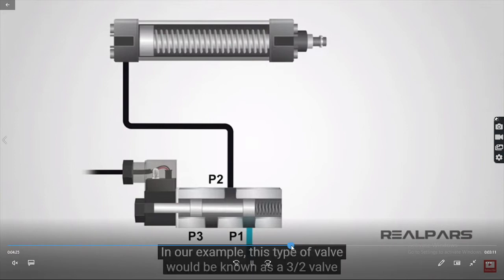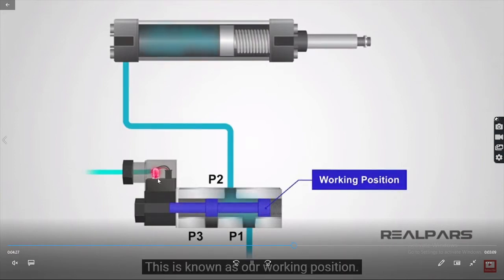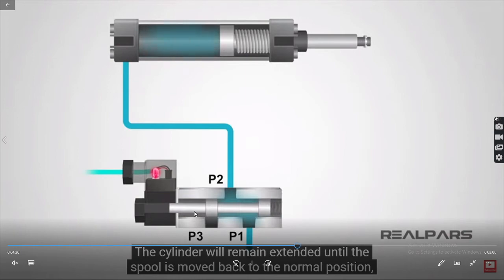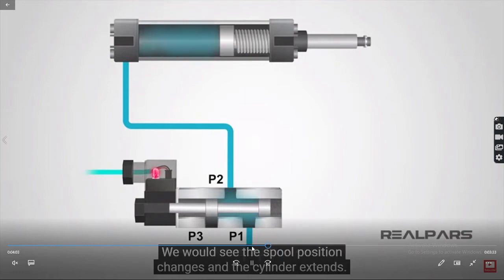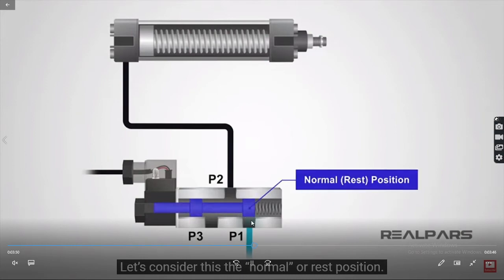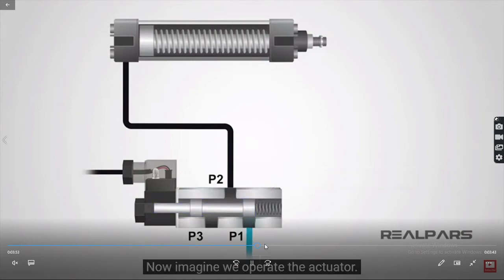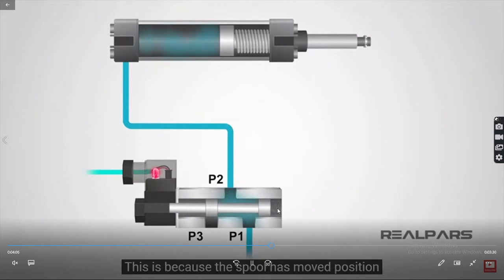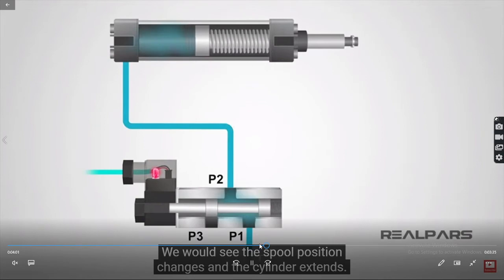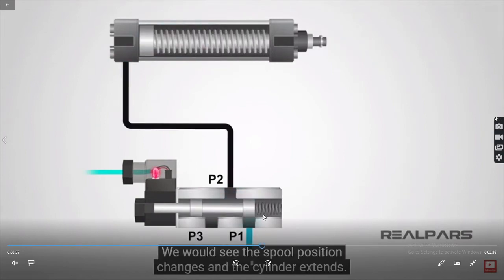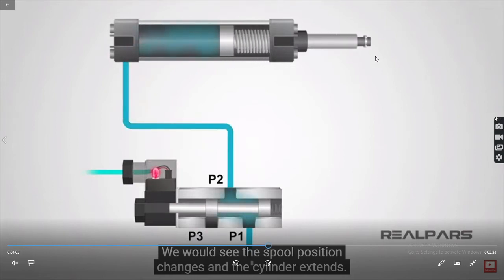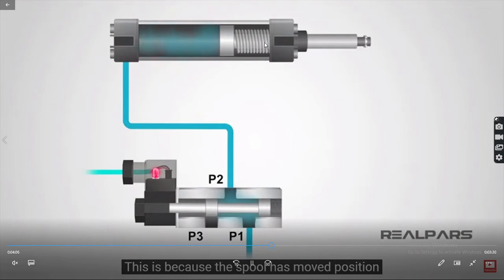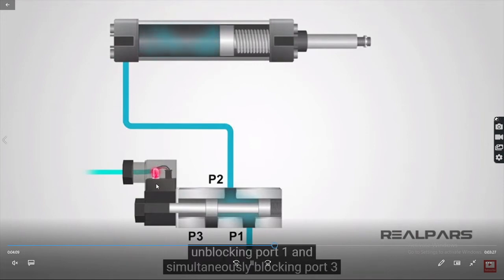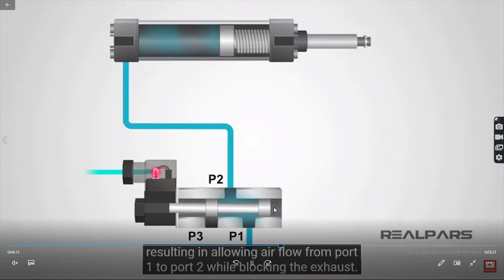See here, when you are actuating, before actuation this is in this rest position, which means the inlet is blocked. When you actuate, this will move to the right side. Now it is moving right. When this moves right, fluid will go like this, and the cylinder will be pushed in this direction. It will remain in that state till this is actuated. Once this becomes off, due to the spring action, this will return here.